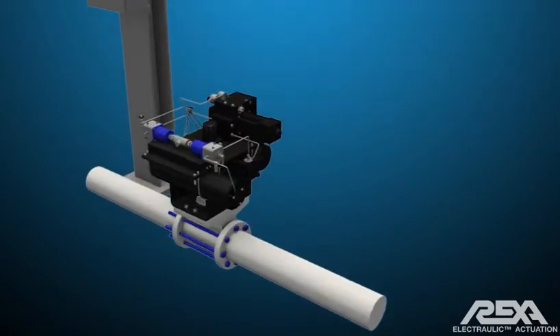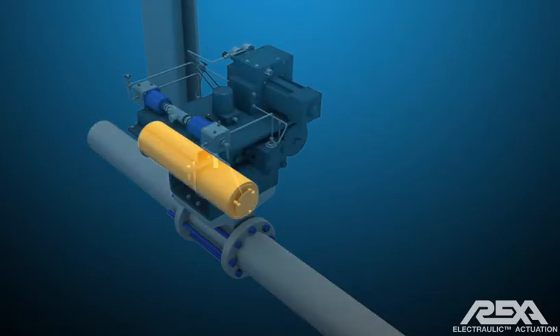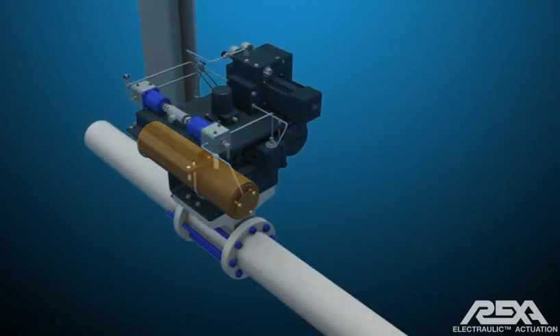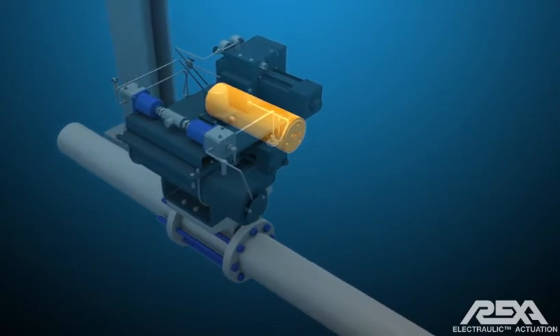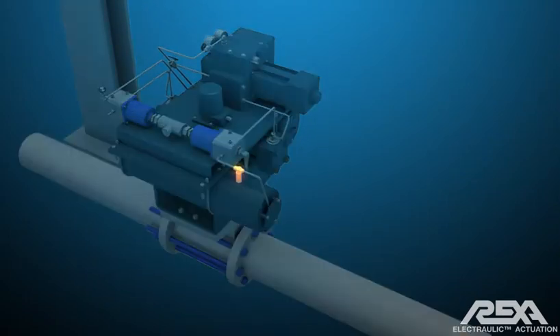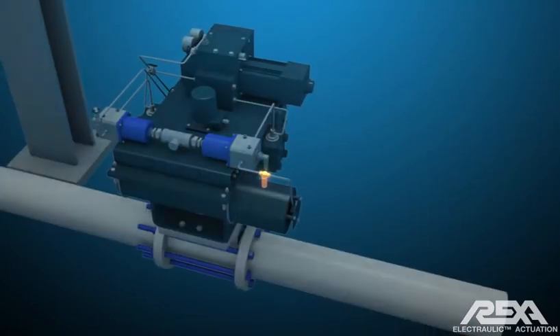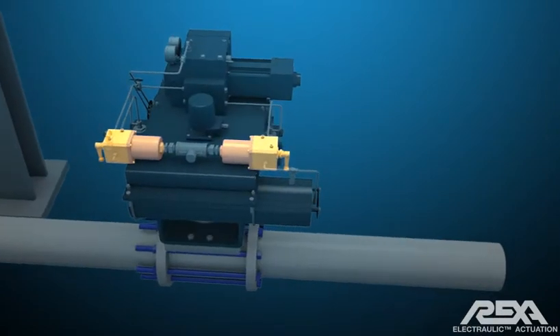Accumulator fail-equipped actuators include a nitrogen-filled piston accumulator, pressurized collection bottle, an accumulator pressure transmitter, and two solenoid-operated valves.